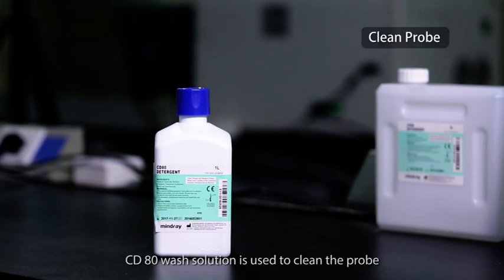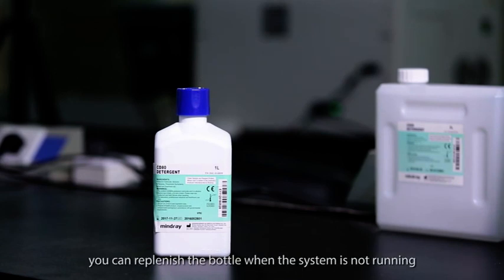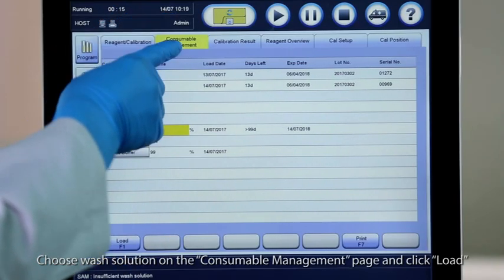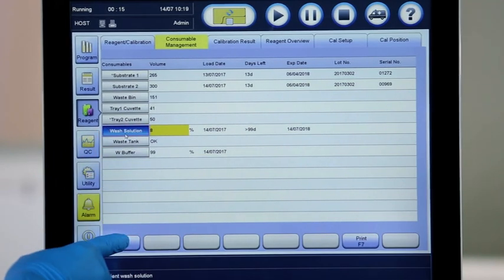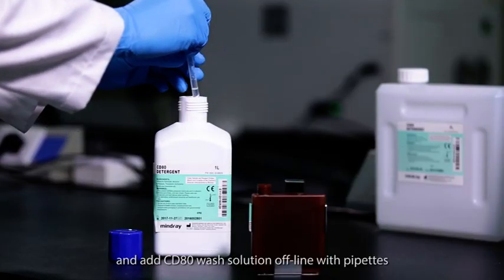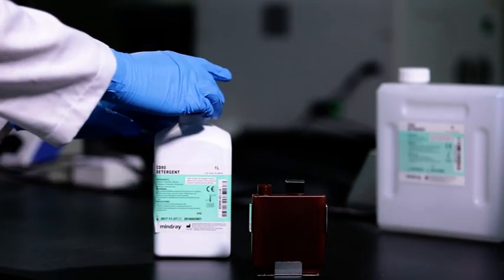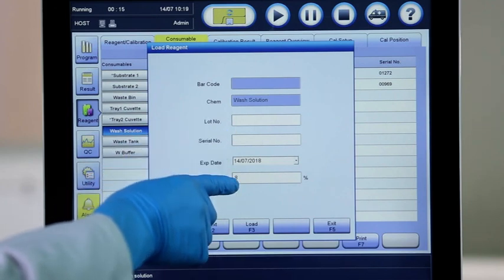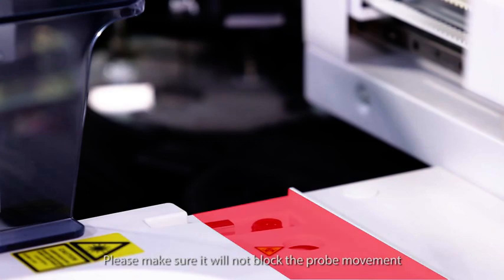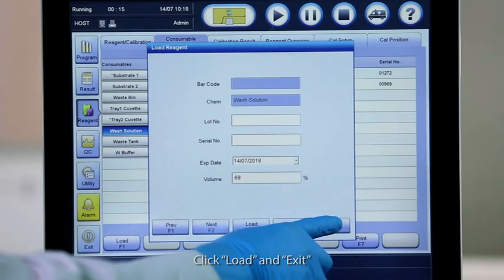CD80 wash solution is used to clean the probe. If the wash solution is used up, you can replenish the bottle when the system is not running in case of probe collision. Choose wash solution on the consumable management page and click load. Take the wash solution bottle out and add CD80 wash solution offline with pipettes. Do not add when bottle is still on the machine. Enter the following information. Put the wash solution bottle back to the position. Please make sure it will not block the probe movement. Click load and exit.